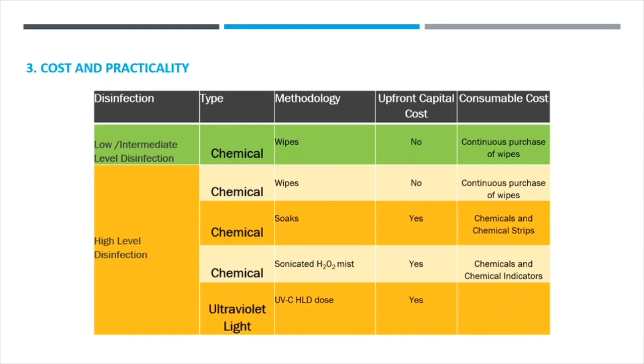One, options exist for high and low level disinfection, both with and without capital expenditure. I fully appreciate how difficult it is to get capital expenditure, but options exist where capital expenditure is not necessary. Second point to make is we went and looked at the costs of what was available in Australia. Now, these are combined costs that take on board capital costs, consumables, and maintenance, and also consider the costs not just of cleaning the probe, but of cleaning the machine, the probe, and the high frequency areas of the machine as a total.